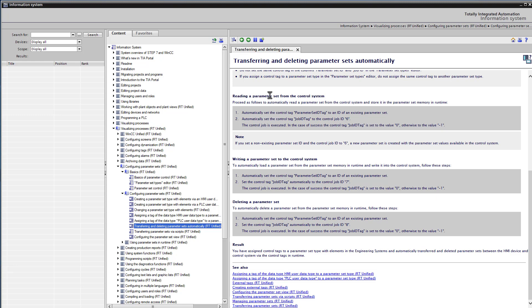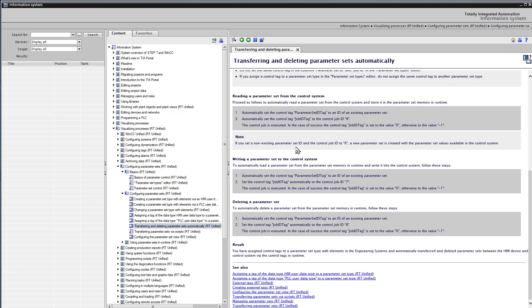it tells you if you want to read a parameter set from the control system, what I think of as upload, it's coming from the PLC and going into your parameter set, then you use job ID of 6. And if you want to load an existing parameter, then the ID value should be the ID number of that parameter set. You can also set a non-existing parameter set and have the process create a brand new parameter set from the values that are in the tags.